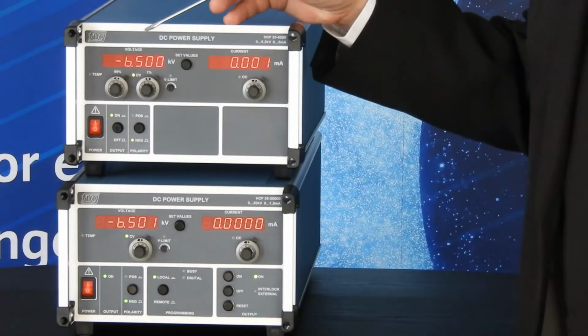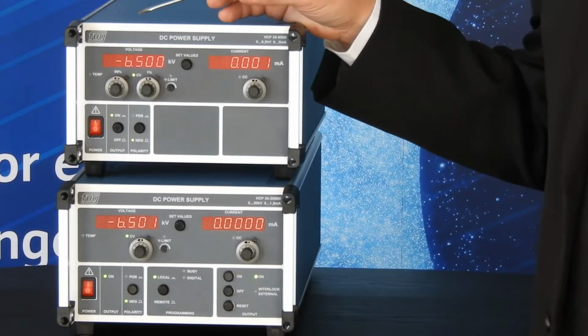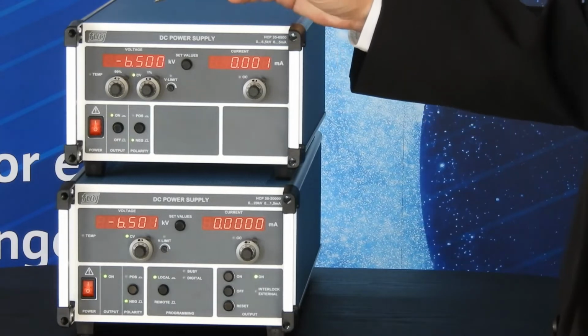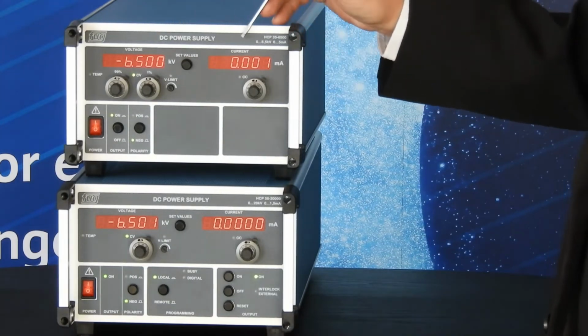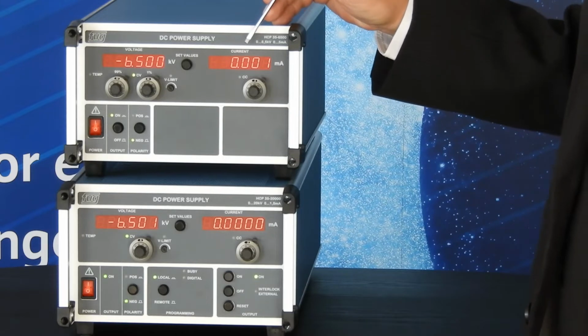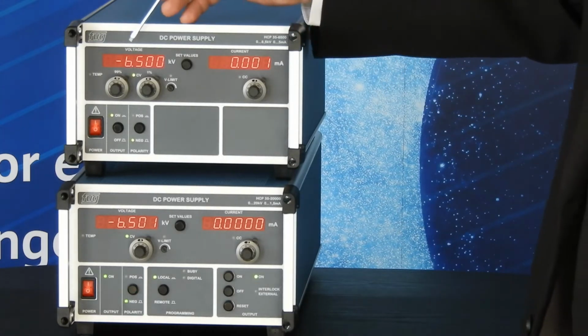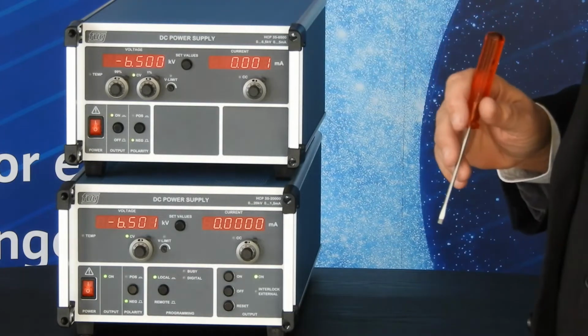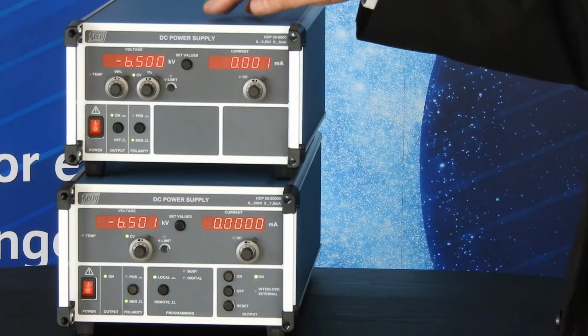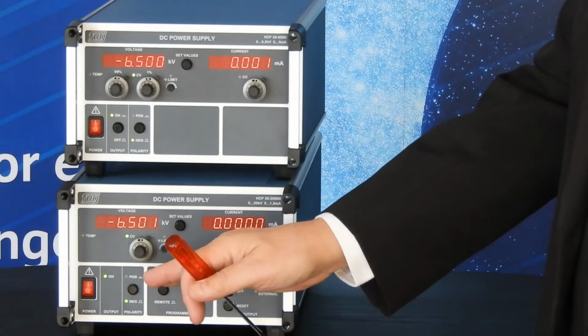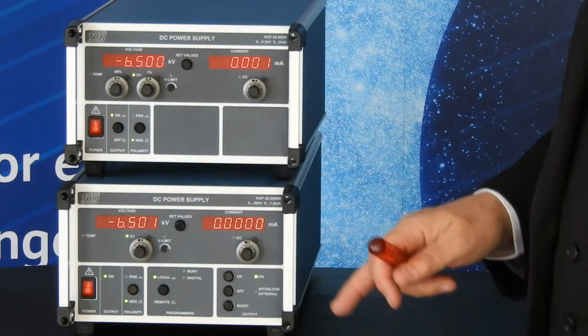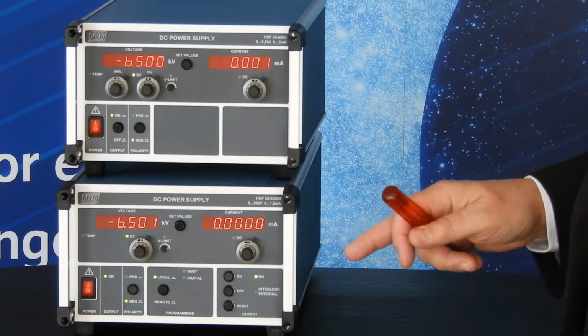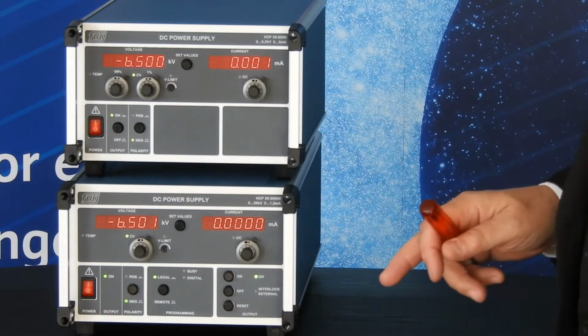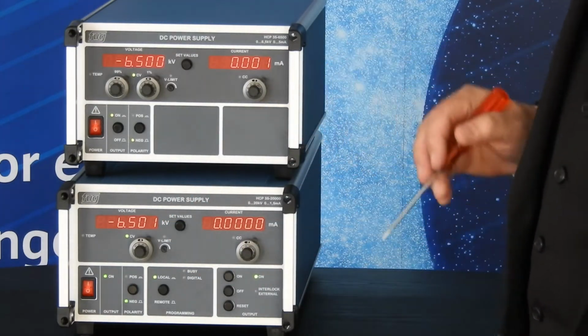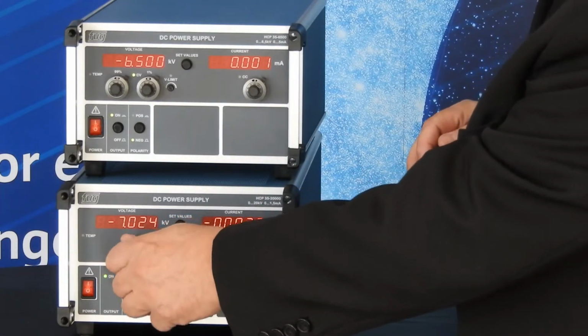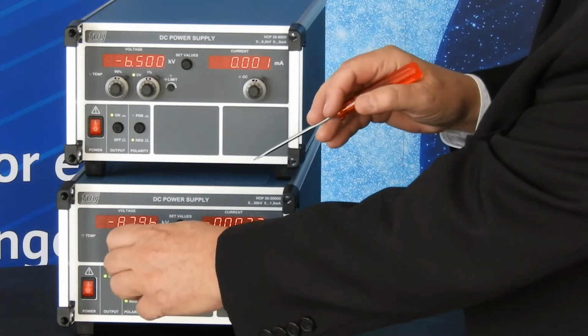Both of the power supplies we see here have a 4.5 digit display for voltage and a 4.5 digit display for current. Let's adjust 6500 volt, the maximum voltage of this power supply. Here I have also adjusted 6500 volt, 6501 in this case, because this one doesn't have the fine potentiometer. But I can adjust more. This power supply can deliver up to 20 kilovolt.